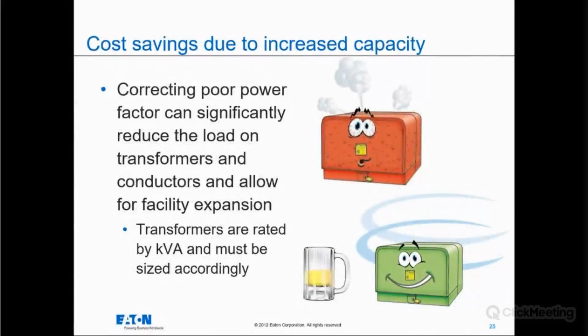And again, another cost savings from power factor would be lowering, as we discussed, the operating temperature of your transformer. Well, how are we doing that? Well, if you remove that kVAR, that reactive power load from your transformer, you're not pulling it through your transformer. You're operating your transformer at a reduced temperature because you're freeing and removing that load from the transformer. So you can see here, this is a representation of that fact that you are removing load, operating it cooler, and which will extend the life of the transformer.